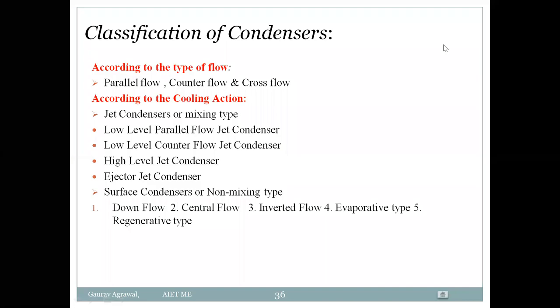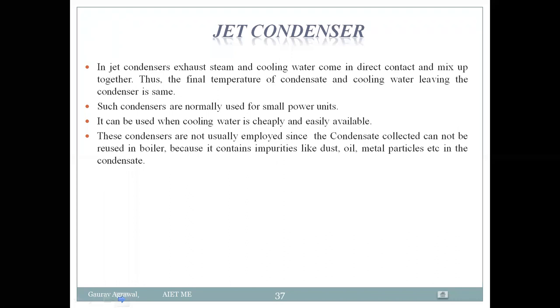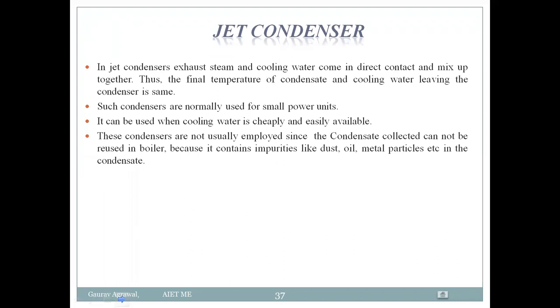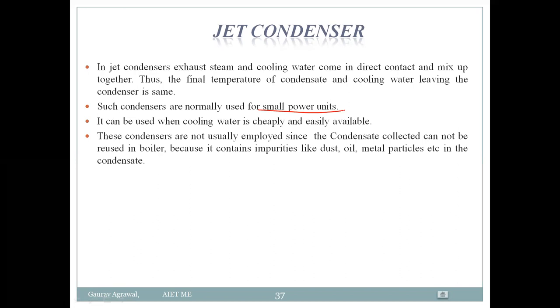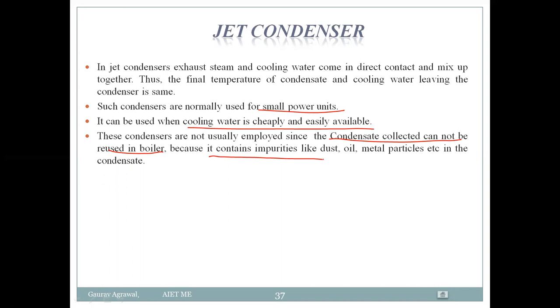We are continuing with the classification of condensers. The jet condenser is generally used in small power plants, and it can be used when cooling water is cheaply and easily available. However, these condensers are not usually employed in large plants since the condensate collected cannot be reused in the boiler because it contains impurities like dust, oil, and metal particles.